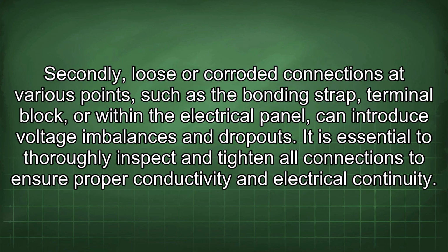leg. Secondly, loose or corroded connections at various points, such as the bonding strap, terminal block, or within the electrical panel, can introduce voltage imbalances and dropouts. It is essential to thoroughly inspect and tighten all connections to ensure proper conductivity and electrical continuity.